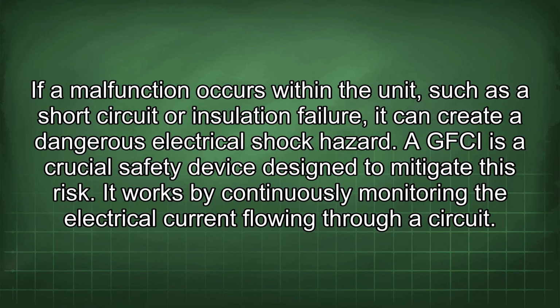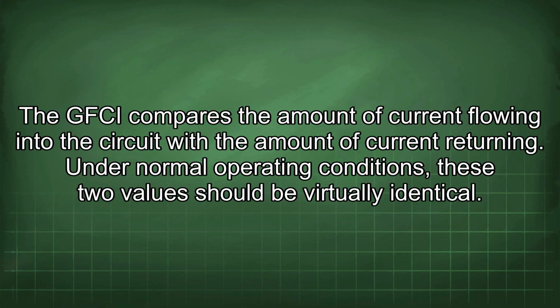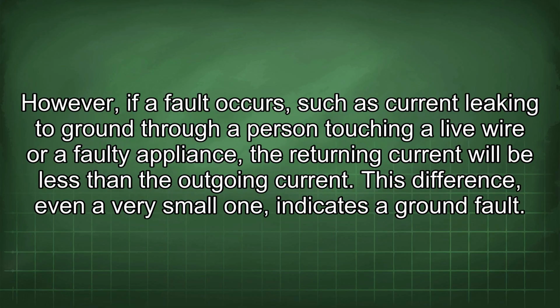It works by continuously monitoring the electrical current flowing through a circuit. The GFCI compares the amount of current flowing into the circuit with the amount of current returning. Under normal operating conditions, these two values should be virtually identical. However, if a fault occurs, such as current leaking to ground through a person touching a live wire or a faulty appliance, the returning current will be less than the outgoing current. This difference, even a very small one, indicates a ground fault.